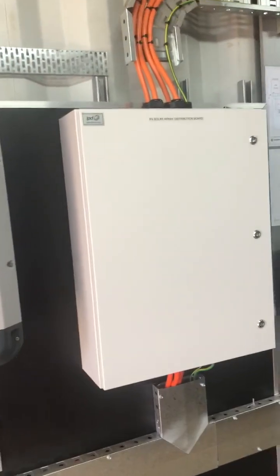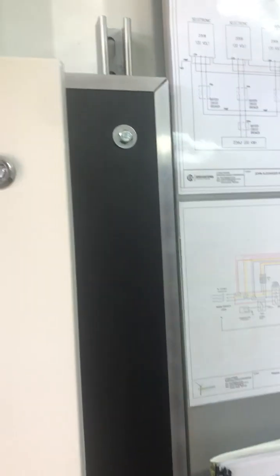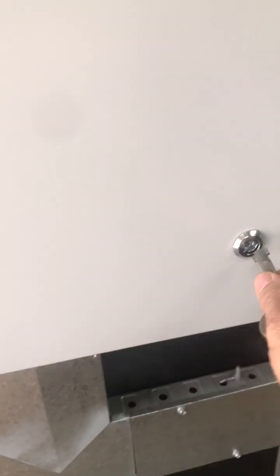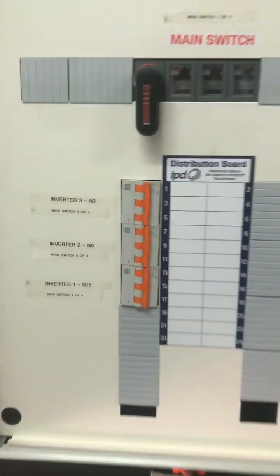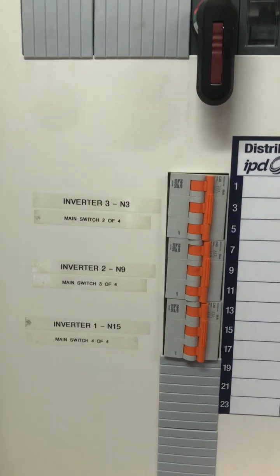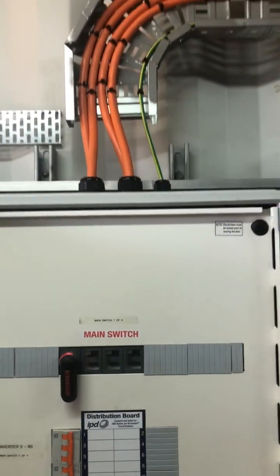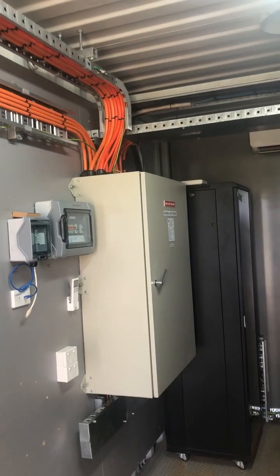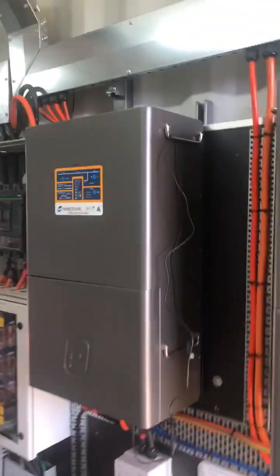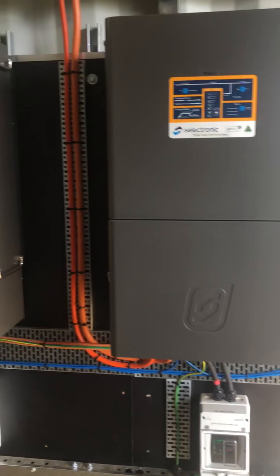So if we go back to the PV distribution board, I'll just open that up. Inside here we have the circuit breakers for each inverter. Then we have a main switch, and then the cables come up out of the distribution board and flow into the main board, which we'll go to in a minute. Then we have quite a few cables coming back from the main board, which connect down into our multi-mode inverters. I have a wiring diagram which will make a little more sense if I show that to you.